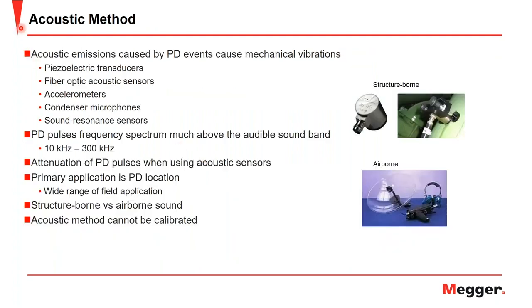Next, we have the acoustic measurement. And the acoustic emissions are caused by the PD events that cause mechanical vibrations. And this can be picked up using piezoelectric transducers, fiber optic acoustic sensors, accelerometers, condenser microphones, or sound resonant sensors.